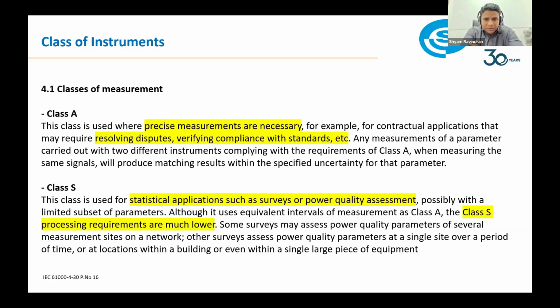In class A, we have a precise measurement, and class S is for statistical applications. So from the user perspective, wherever you want to talk to a legal authority, for example a customer in discussion with a public utility, it is class A. When it's only an industrial manager wanting to make a statistical application survey within their premises, usually it is class S. The processing speed within class S, from an equipment point of view, will be significantly smaller compared to class A equipment. From the commercial perspective, class A is also significantly more expensive compared to class S.